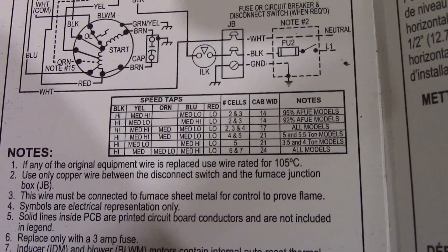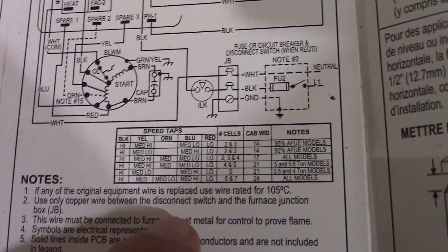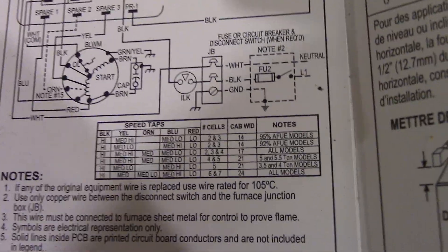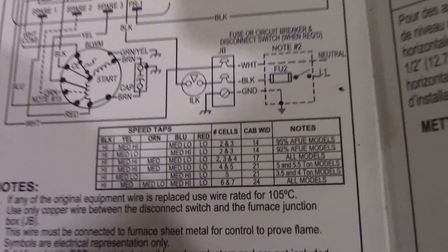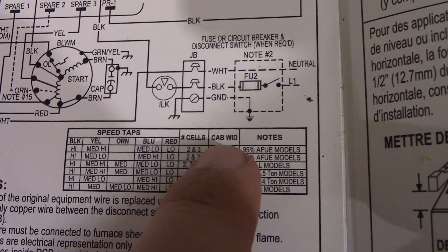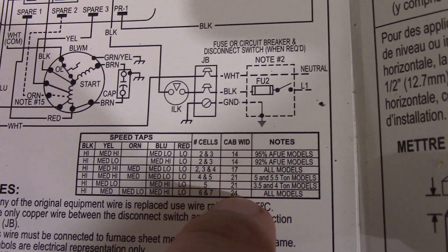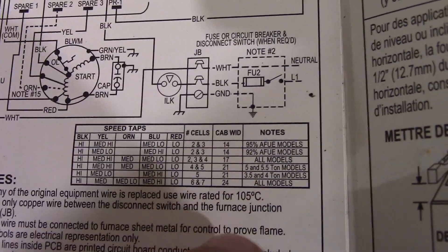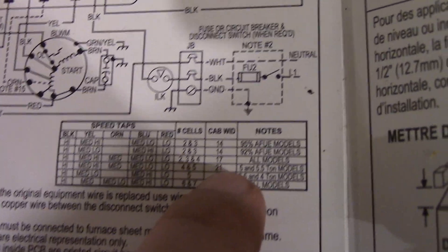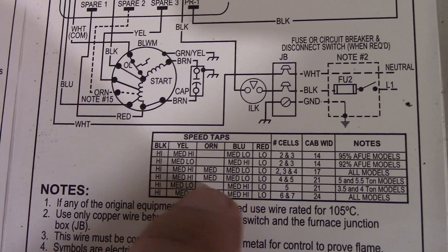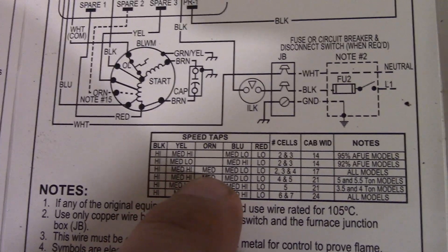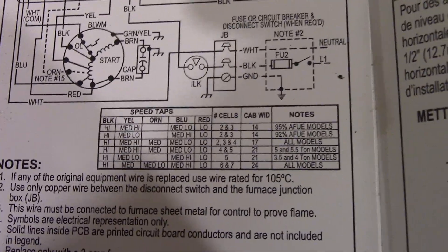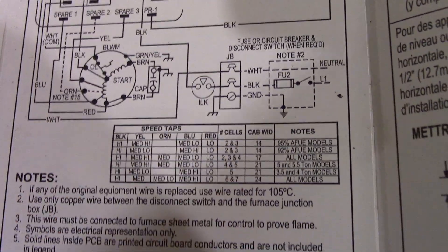Right away, I can rule out three of these, because three of them indicate that there's no orange wire. We have an orange wire, so we know those three don't apply. The other thing I was able to use was cabinet width. I measured the cabinet and it came out to just about 17 inches. So if you have a 17-inch cabinet, all models, the standard in between ones apply. Yellow is medium-high, orange is medium, and blue is medium-low. That's how you can figure your speeds out with use of the diagram and chart.